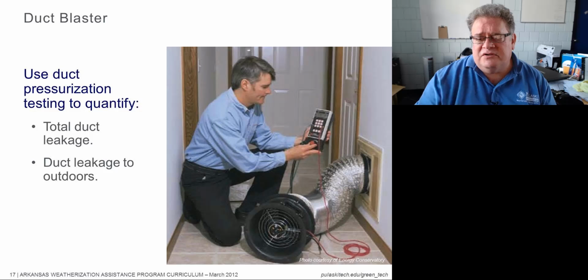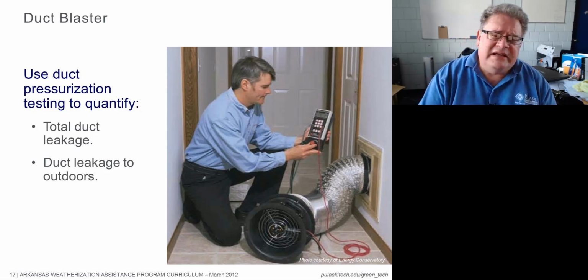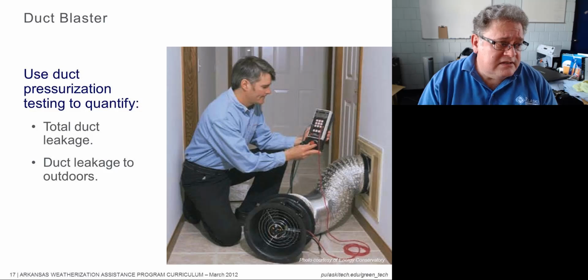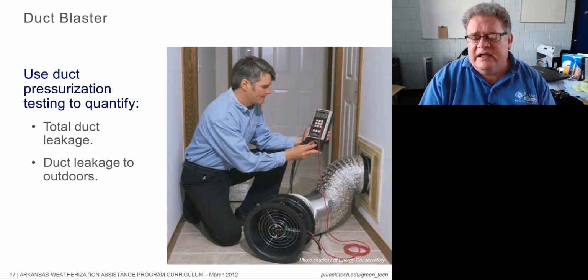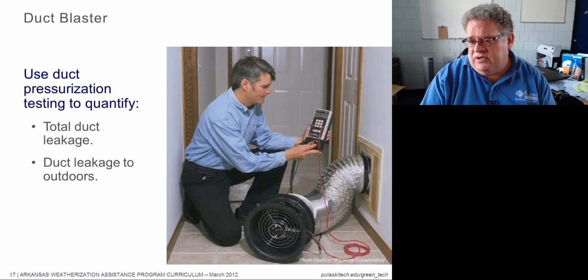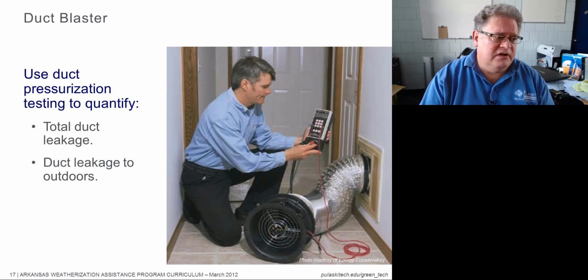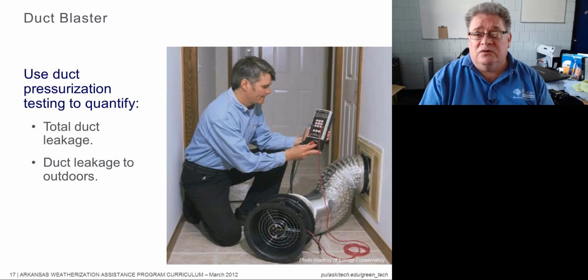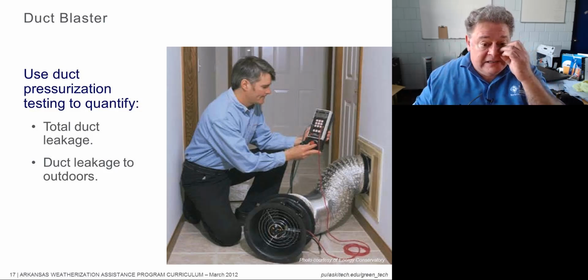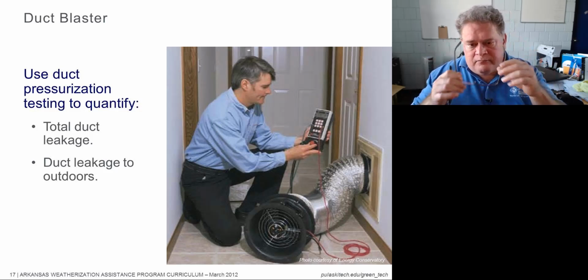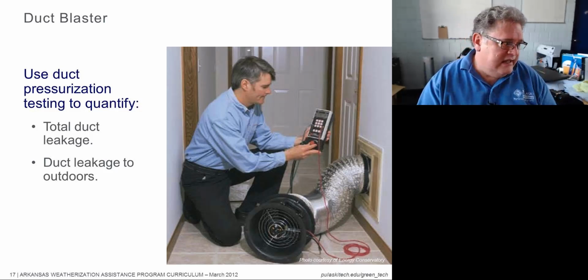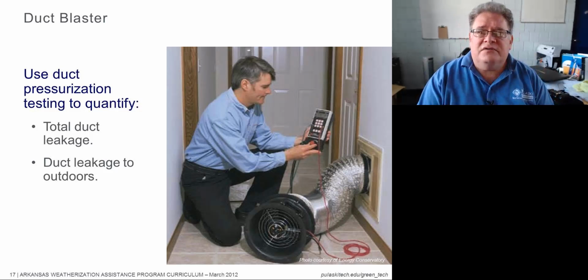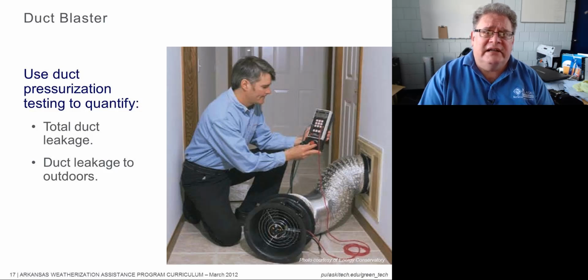Normally we want to measure total leakage to the outdoors. Some agencies don't use both. Some agencies do use both. Some use one or the other. If your agency doesn't use a duct blower, that's okay too. If you're in a program that does use a duct blower, you're probably measuring total leakage to the outside. If you're using NEAT, that's probably the preferred way to test ducts. And do your agency and yourself a favor. Start testing those ducts if you're running NEAT, because there's a lot more dollars available with an accurate test on a duct blower than there is with a pressure pan.